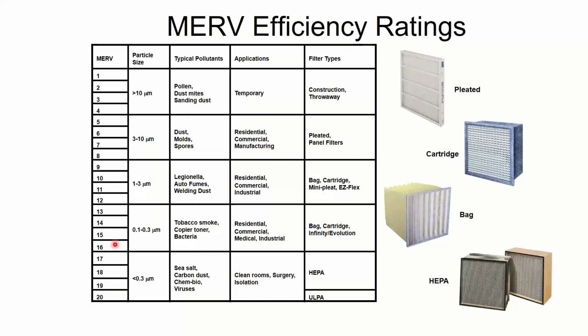Can you use a MERV 15 or 18 or 20? Yeah, sure, you can. Now, generally speaking, as you move up higher in MERV rating, you're also going to have more pressure drop. If you want to put HEPA filters in, that's awesome. It'll catch a virus if it gets back to the filter, but it's going to be a pretty decent airflow penalty. So 14 is kind of a sweet spot. MERV 15 maybe, if you can do that.